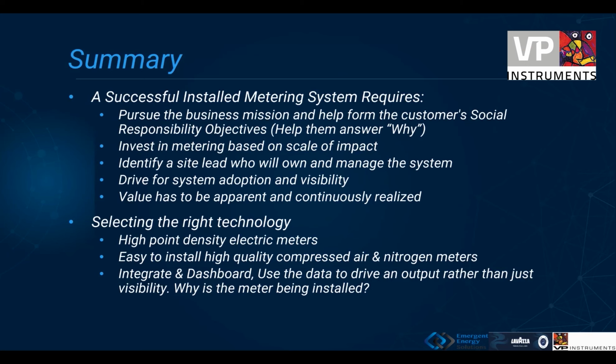When a customer wants to put a meter at a location that is continuous use, with no significant change and really nothing they can do with that data afterwards, I usually recommend against it. I always like to recommend installing meters at points that have high variability, where it's going to make something really apparent so they can make an important decision that makes their process better.